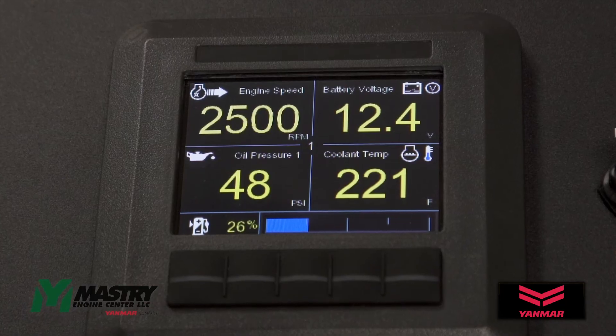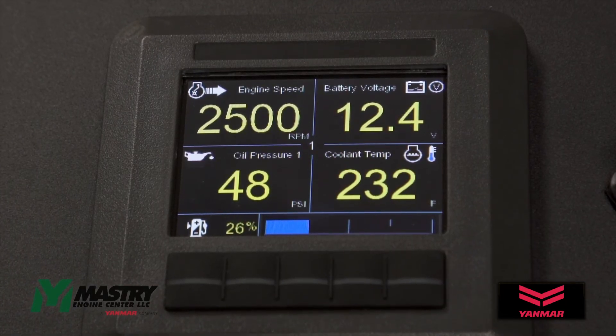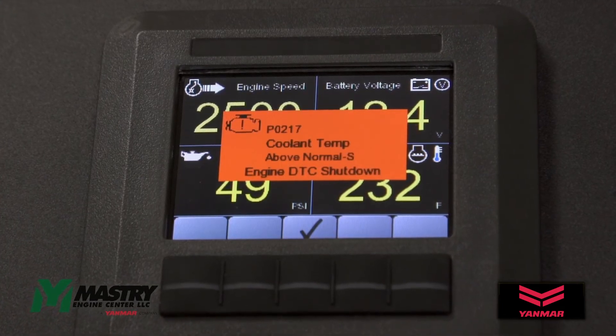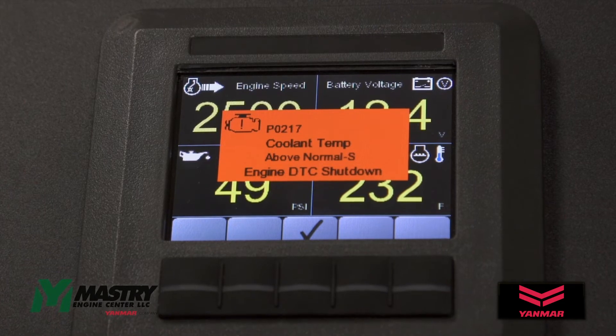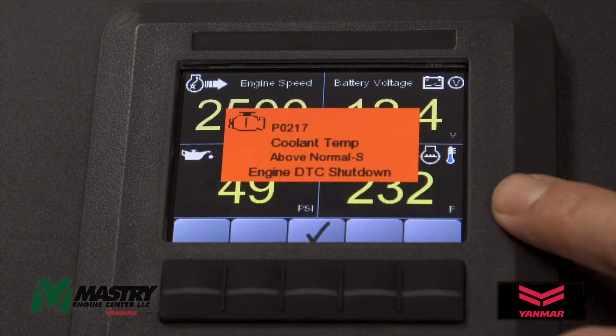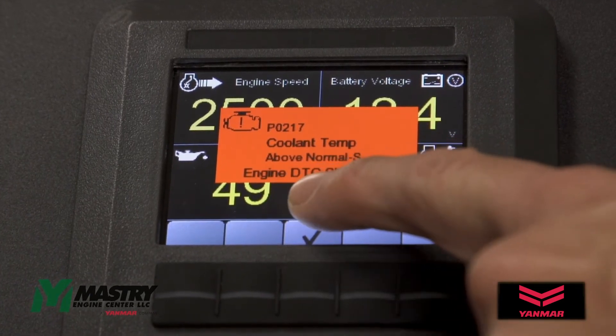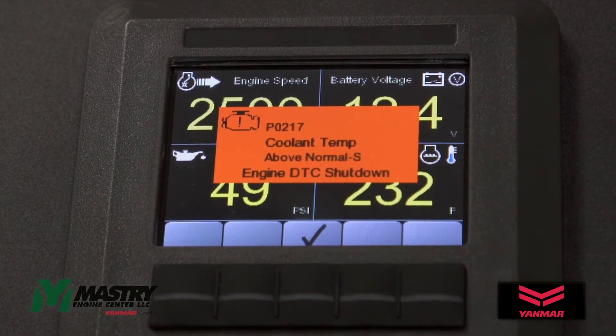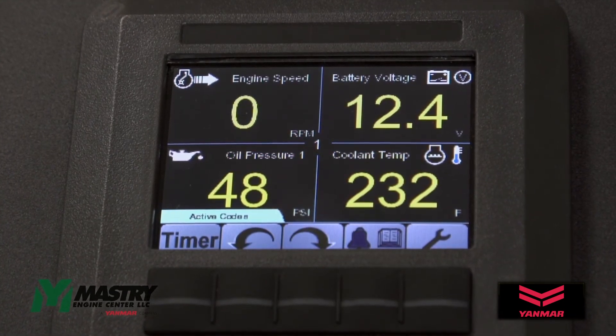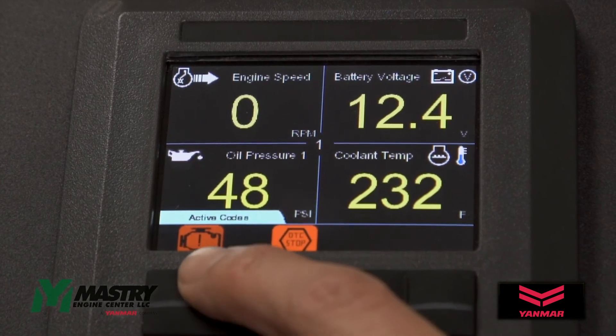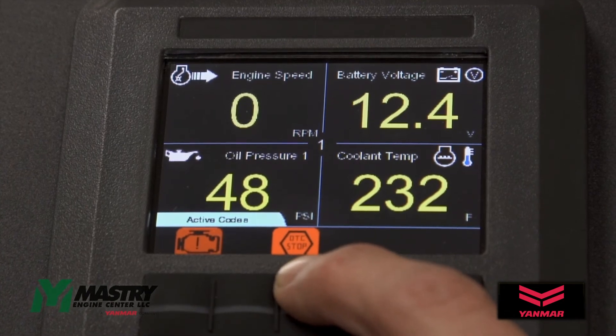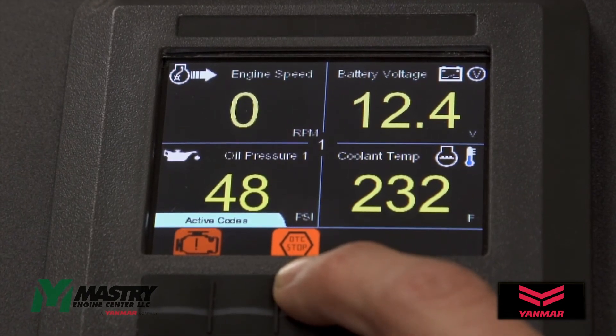If the engine temperature exceeds 230 degrees Fahrenheit, you will get a diagnostic trouble code for high coolant temperature, and the engine will shut down in order to protect the engine. A fault code like this will pop up, and what's different about this fault code versus a regular fault code is the text at the bottom that says engine DTC shutdown. You can acknowledge this fault code, and then you'll see the engine speed has dropped to zero, and now we have an active fault code icon, but we also have a DTC stop icon indicating that this particular fault code has shut down the engine.